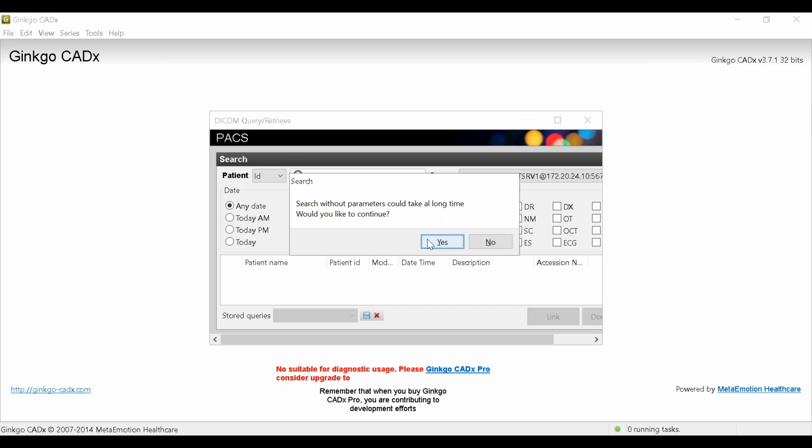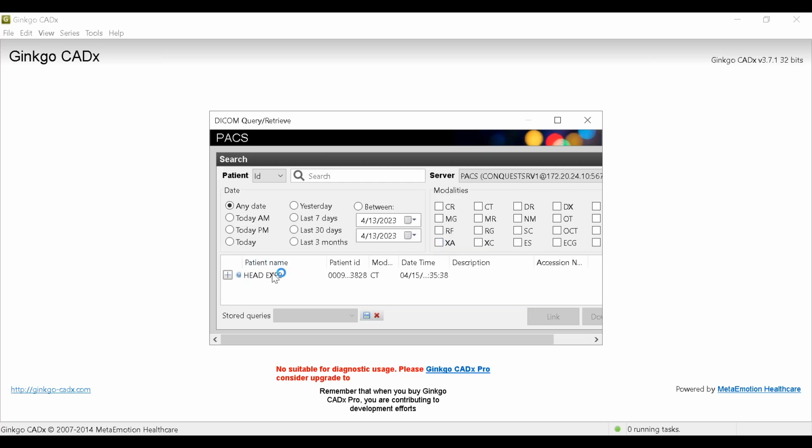We know we got two things in our archive. Just go ahead and click yes. Notice here it gave me some information. It says patient head X2. Notice this is not on the server software. This is on the client software. This could be on a different machine. All we had to do is change the IP, but have that machine with that IP on the network able to see this one. Essentially, at this point in time, folks, we've succeeded.